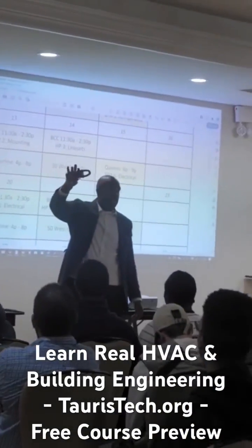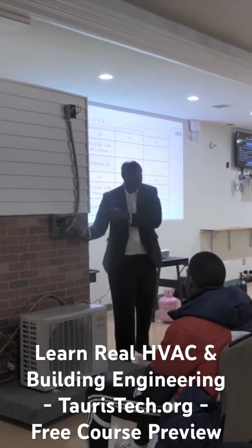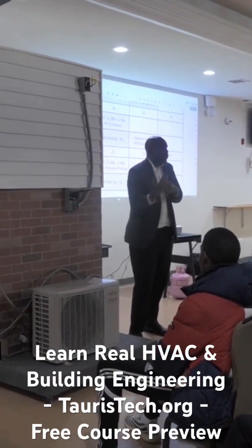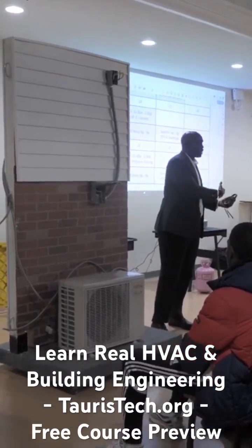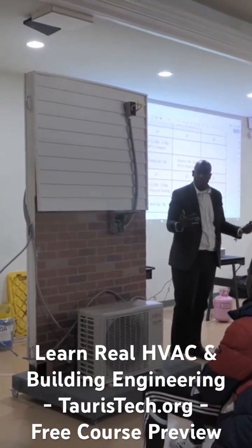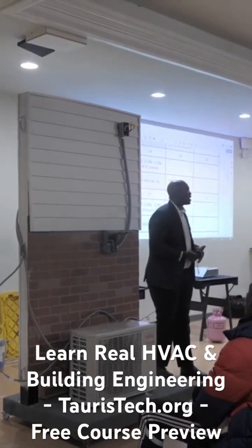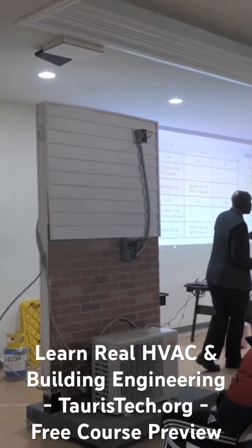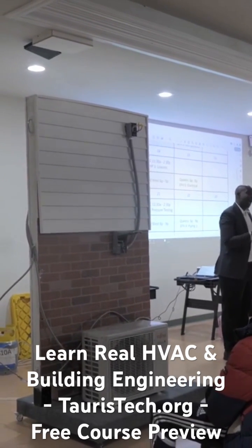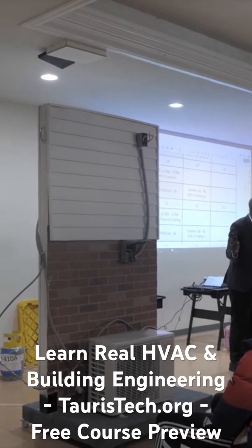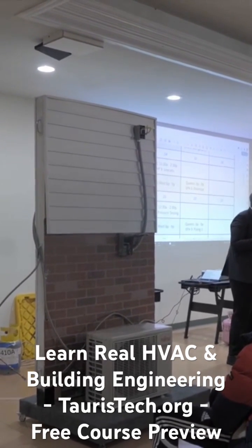Does anybody know what this is? It's a multimeter because we can use it to measure amps and volts and ohms and continuity. If this was live and I touched this and he came along and he tried to grab me to pull it off, now we create a circuit and he's going to get hurt. So it goes beyond just protecting myself. I need to protect the people that I'm working with as well. Whether or not you can give me the dictionary definition of what a volt or amp is, I don't care. I care that before I touch that equipment, I tell you to give me that reading, you're telling me whether that circuit is live so I don't hurt myself.